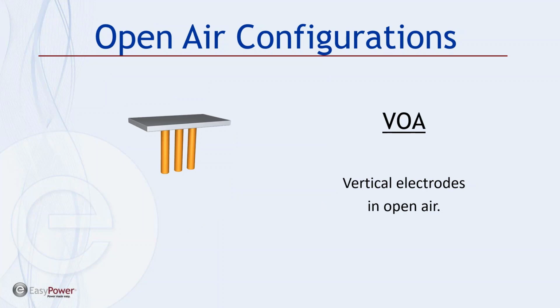Then in the open air configuration, again, this is basically defined as the operator standing, from our perspective, to the side of the electrodes, and there's no exposure beneath them. And if we look at the examples in the standard of the radiation pattern, it actually goes down more so than out at the operator.